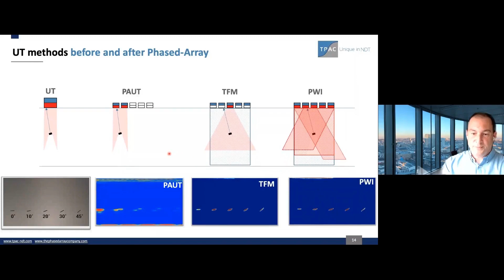In TFM, we shoot element by element, and we capture all the signals that we get in the different elements. In this way, we can produce a high resolution image. In the case of PWI, we can get this imaging much faster, as instead of triggering element by element, we can generate flat plane waves in different directions and still do a TFM image. So we can get image quality up to the level of TFM in a much faster way. We can even get a higher speed than the one we can get in phase array UT.